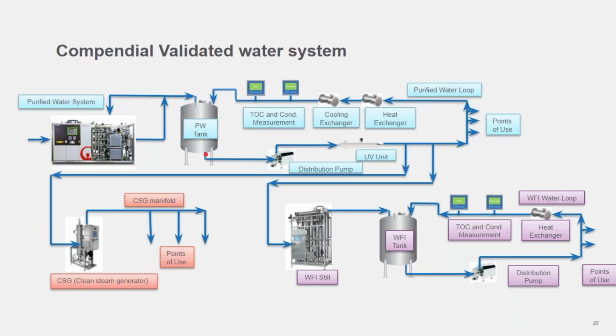Then if we go into the storage tank and the distribution loop, in this particular case this distribution loop is a hot water sanitizable distribution loop, hence the heating and cooling exchangers. The other option is to have an ozonated loop, so you continuously ozonate the tank and destruct the ozone before it gets to the points of use. During normal service, we try to keep the distribution loop below 20 degrees, around about 18 degrees, again to help reduce any microbial growth within the loop. Also, we have a UV unit to manage any prevailing bugs or bacteria that may be in the system, to keep the whole system well within specification, so there's very little risk to the water not being of quality at the points of use.